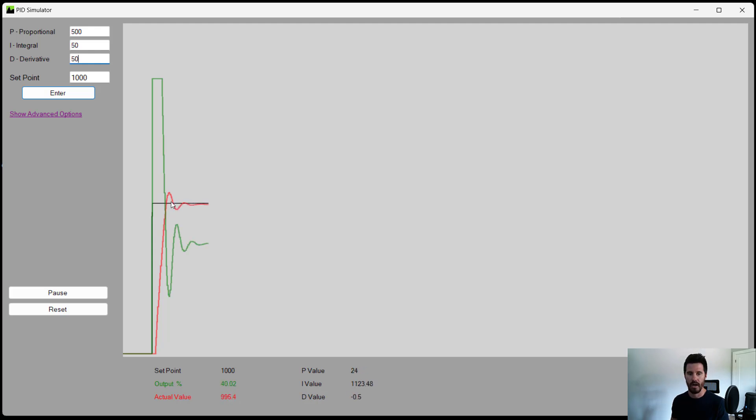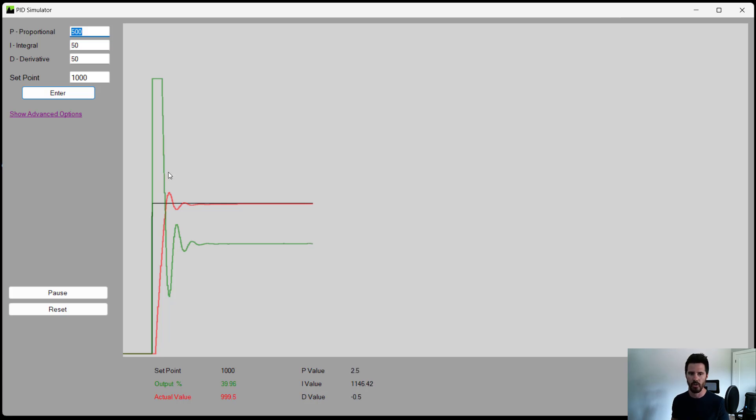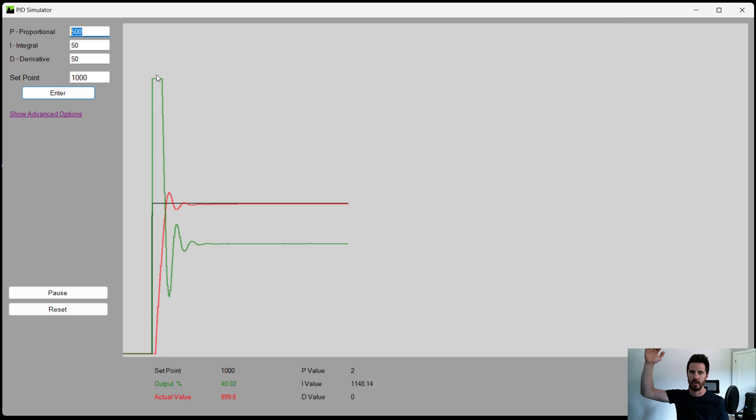Now we can go higher, but the problem is too high of a D value can actually cause some unstable controller. So what I would recommend if we want to limit this last bit of overshoot, we can reduce our proportional a little bit because that is quite a big initial reaction. It puts our output right to 100 and it holds it there for a while. So let's bring the proportional back down.